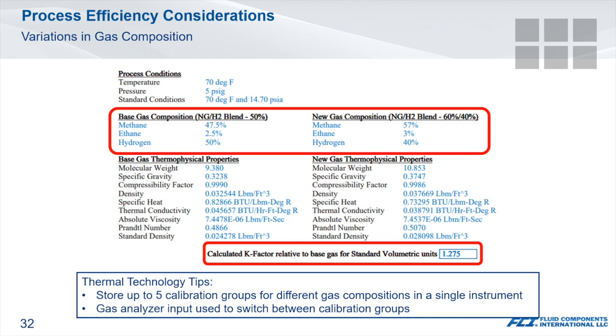Given its unique properties, even small variations in the amount of hydrogen will have an impact on measurement repeatability. To help ensure accurate and repeatable measurements, technologies exist that have the capability of storing multiple calibrations to optimize performance. In many cases, input from a gas analyzer can be used to switch to a calibration that best represents the current gas composition. This approach minimizes inaccuracies related to the specific thermophysical properties of a given composition when compared to a baseline calibration.